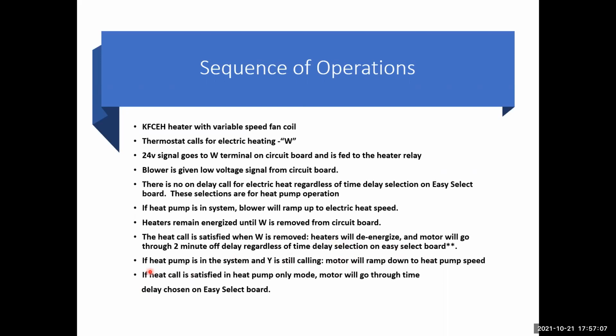If a heat pump is in the system and the Y is calling, the motor will ramp down to the heat pump speed. So what that's saying is if there's still a call and it no longer needs resistance heat, it will go down to the heat pump style of speed instead of the electric heat. If heat is satisfied at the heat pump only, the motor will go through the delay chosen on the easy board.